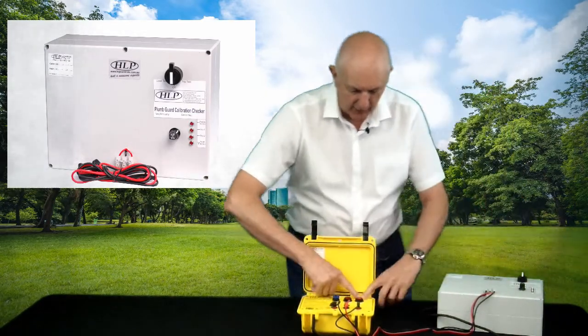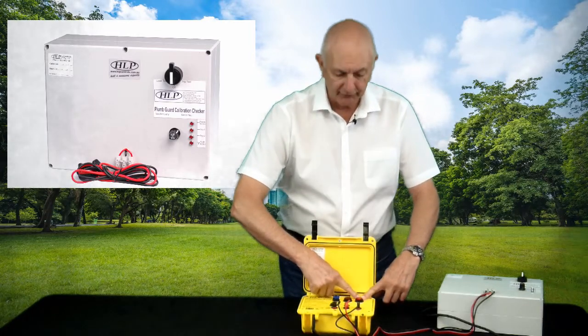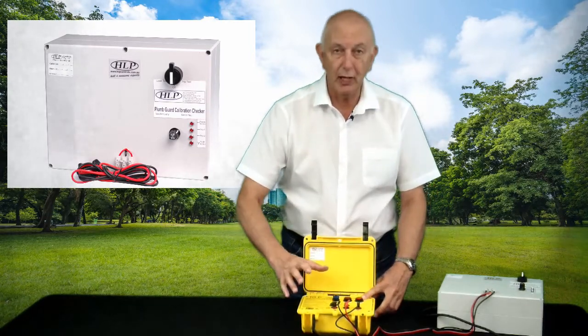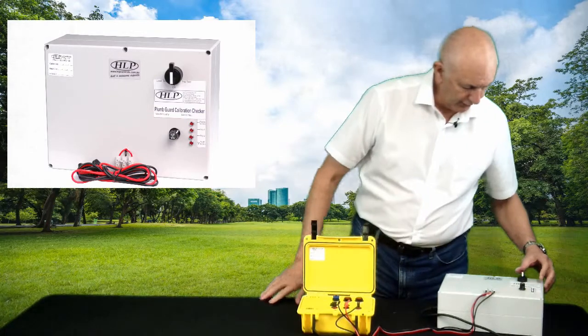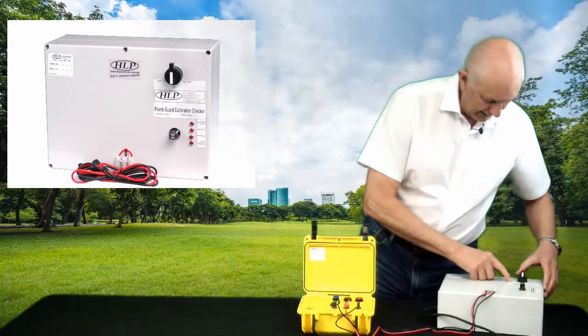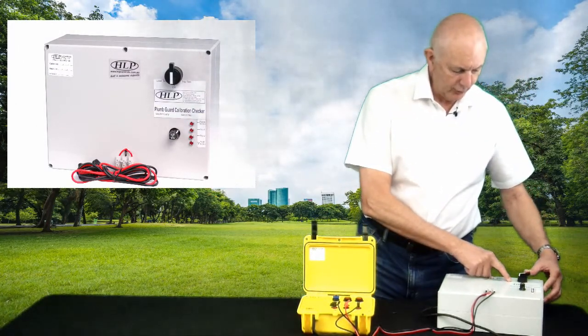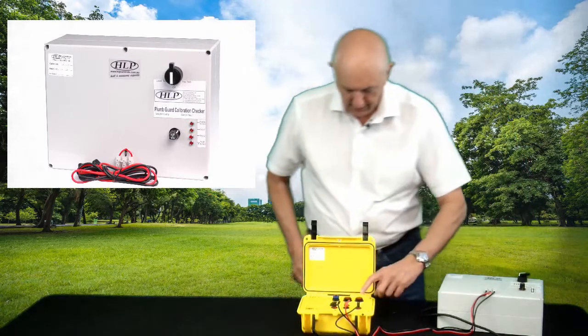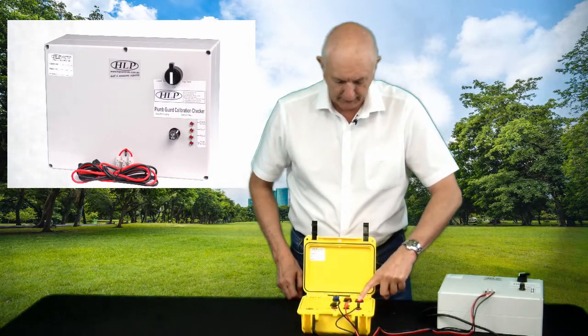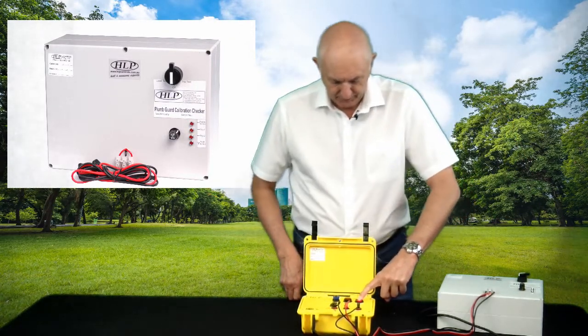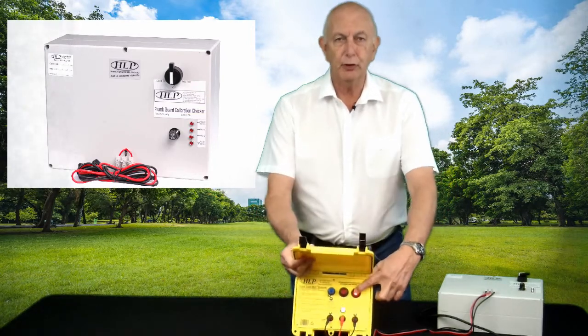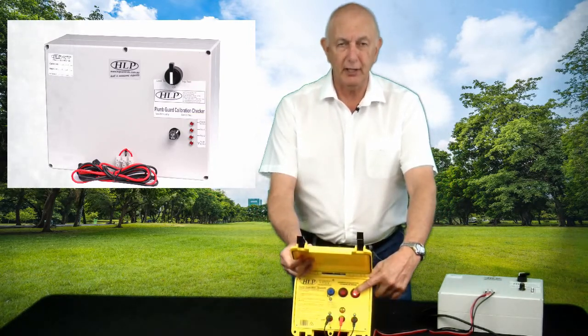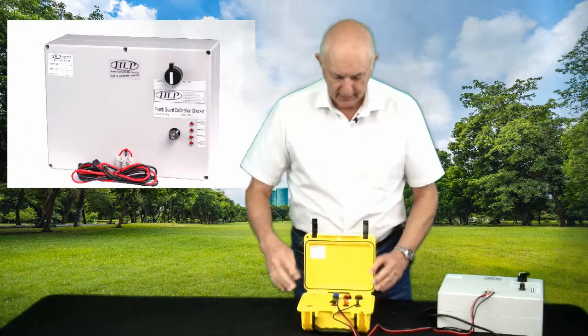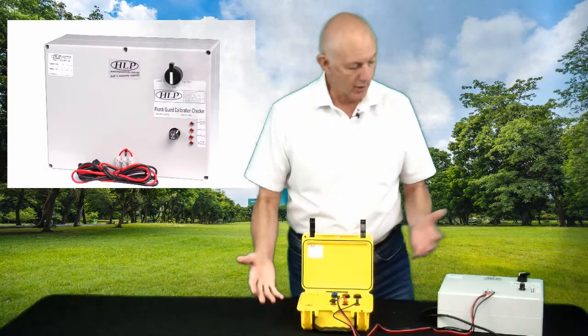So the Plumb Guard is now waiting for a self-check and a self-test of the leads before it will go into run mode. So to do that, we have a lead test switch. So we push the lead test switch on, and then we can push the normal test switch on the Plumb Guard. So that will do its normal self-check, and it says that all 3 leads are working. So the Plumb Guard is now in run mode.